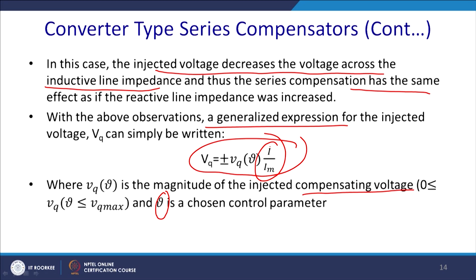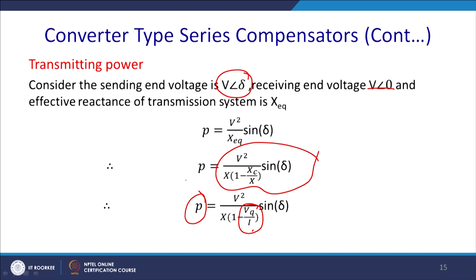So, what happens with this type of compensation with the power transmission? Considering that the sending end voltage is V angle 0 and the receiving end is V angle delta, and the effective inductance is X effective, P equals V square by X effective into sin delta, and thus it is V square by X1 minus XC sin delta, and here we will be replacing XC, because it is a function of VQ here. So, we can write V square by X1 minus VQ by I into sin delta. So, you can see that this quantity plays an important role to control the sending and receiving end power. VQ is a variable quantity and you can control it, and thus you can control the power flow in the transmission line, and you are not touching the value of the current.